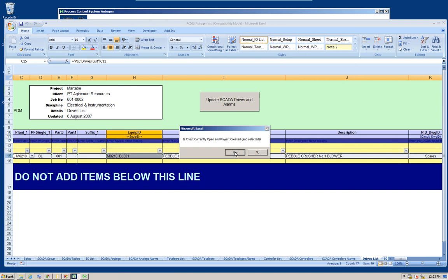So for that purpose we need to have Citect open so that the auto generation program can access the graphics builder functions built into the Citect. Citect has a programmer interface to programmatically generate graphics from genies, and so have many other SCADA products, like iFix has as well a programmatical interface to generate SCADA graphics by calling functions to do that.